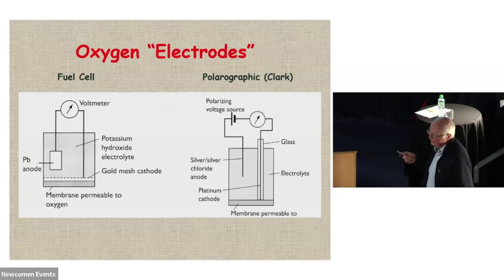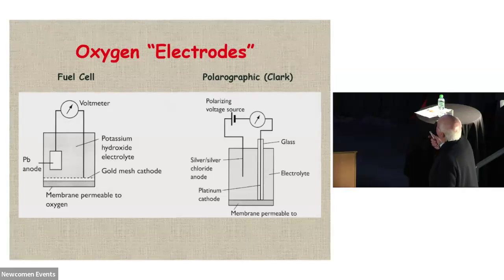All well and good, but they need to be replaced. The cell needs to be replaced about once a year because, of course, it being a fuel cell, it gets worn out. The other type of cell was called the polarographic version, which is often known by the inventor's name, Clark. Half the time you'll find the word Clark with an E on it, but I'm pretty sure that there's no E, and I've spelled it correctly.